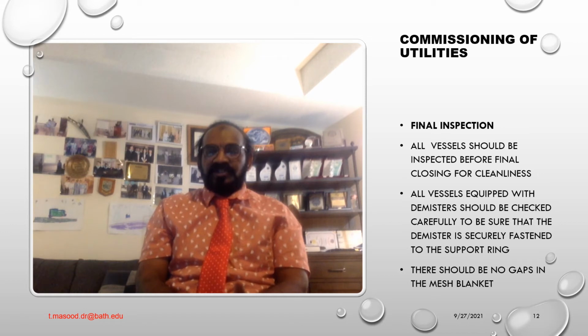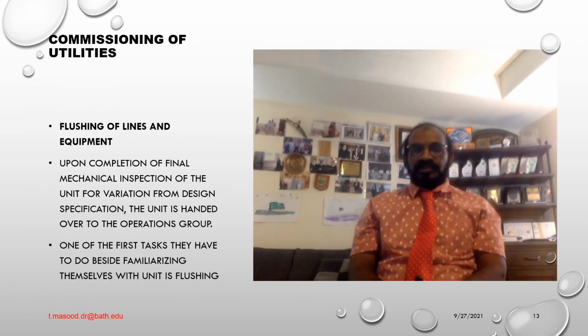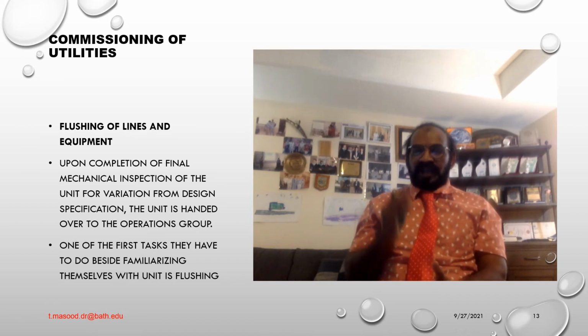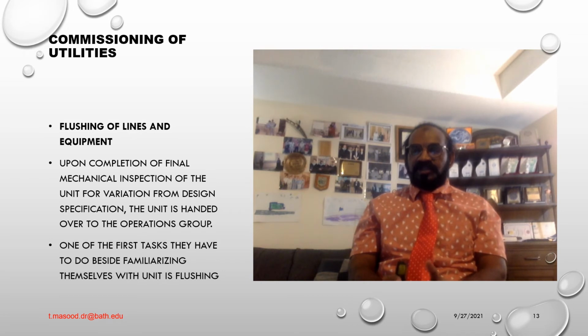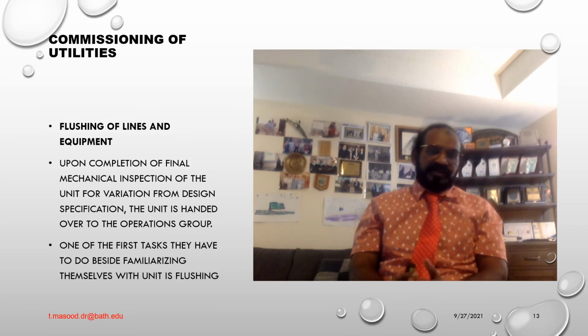Okay, next is flushing of the lines and equipment. Commissioning of utilities, flushing of lines and equipment. Upon completion of final mechanical inspection of the unit for variations from design specification, the unit is handed over to the operation group. One of the first tasks they have to do, besides familiarizing themselves with the unit, is flushing. During flushing, all piping and equipment not previously cleaned is flushed with clean water. A typical reactor, regenerator, column, vessels, and heaters have already been cleaned as a part of the final mechanical inspection.